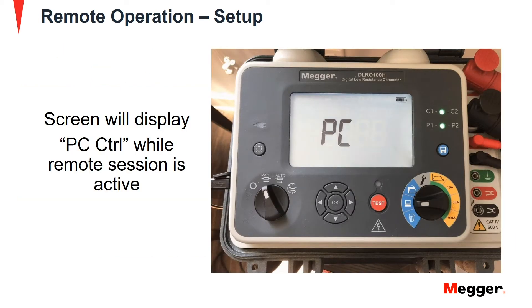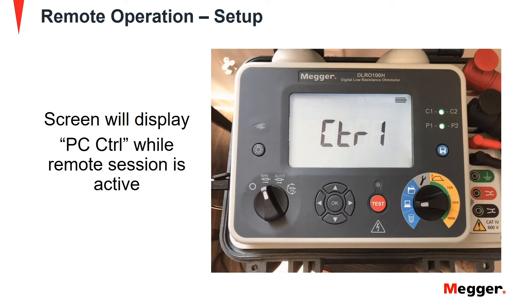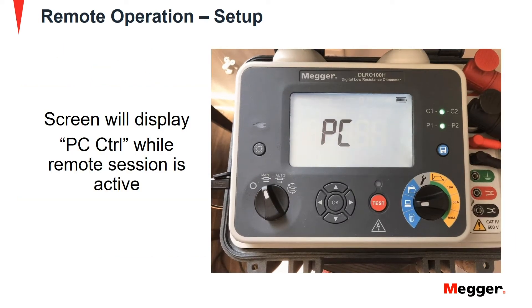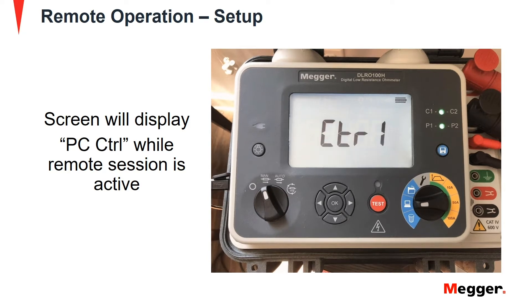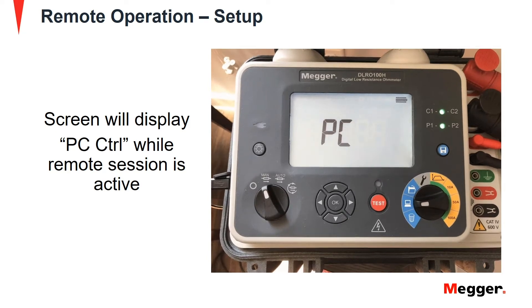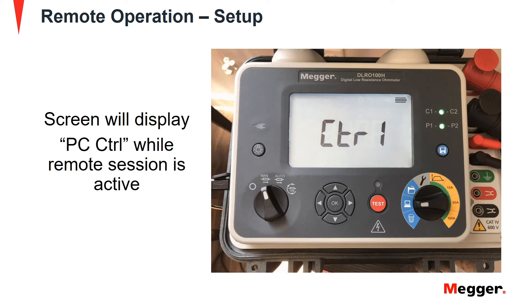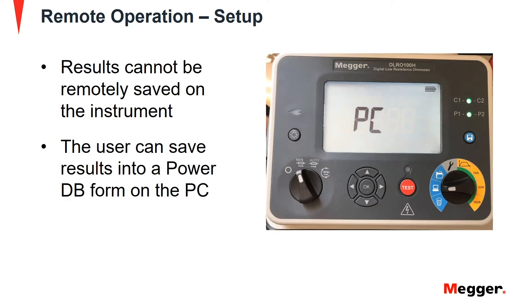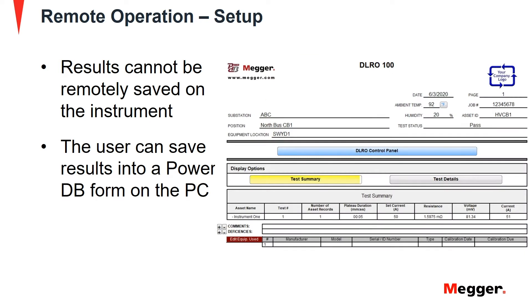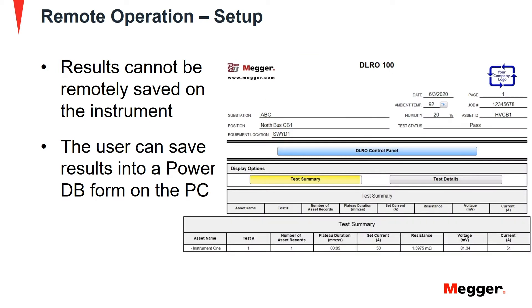When using the DLRO100 remotely, the test instrument screen will show PC control on it. One important aspect to understand in the setup for remote operation is that the results from a remote session cannot be saved on the instrument. The user will have to save the results into a PowerDB form on the PC.